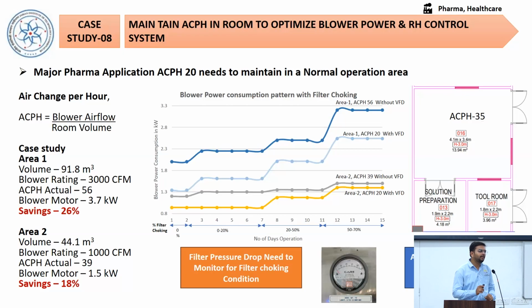Main load is pharma, the HVAC load only. So we measured the ACPH in every area. We found that some areas have higher ACPH than required. Blowers are always designed to achieve ACPH even in the worst condition of the filters.